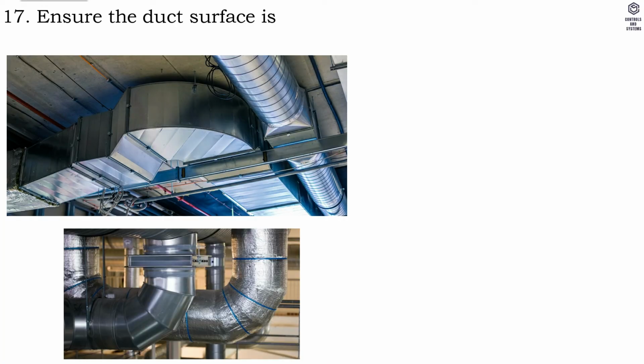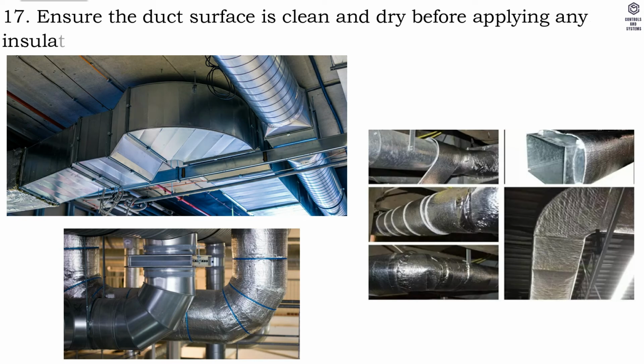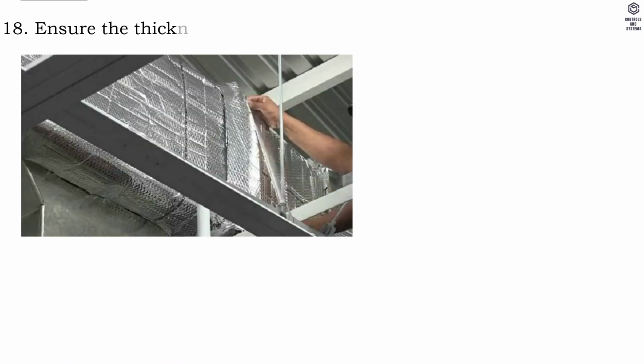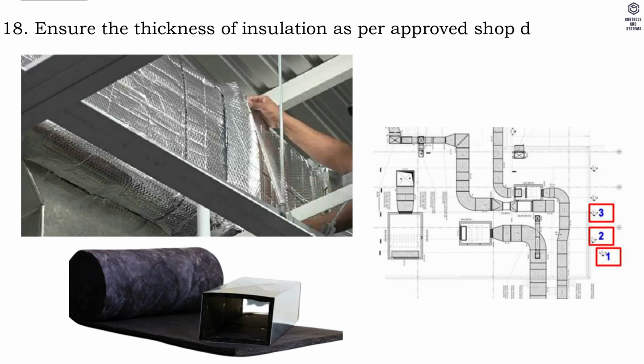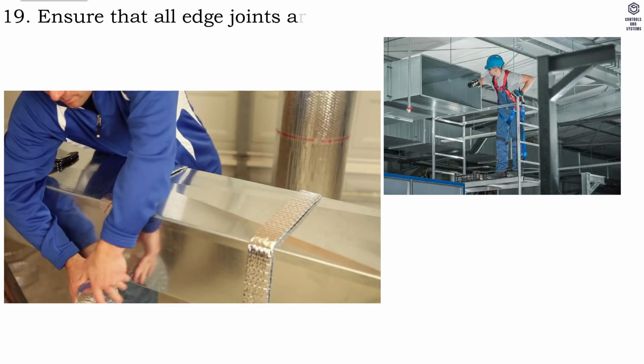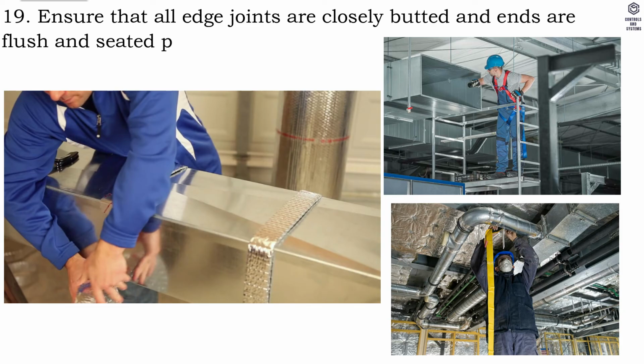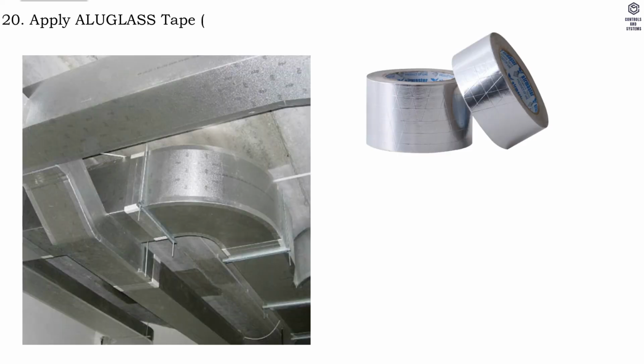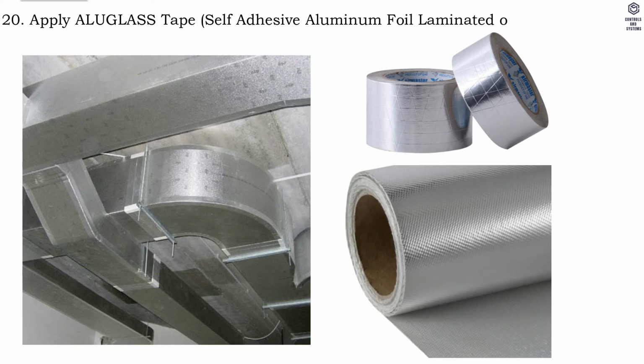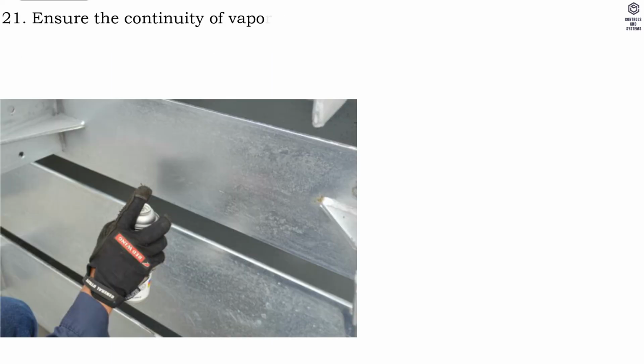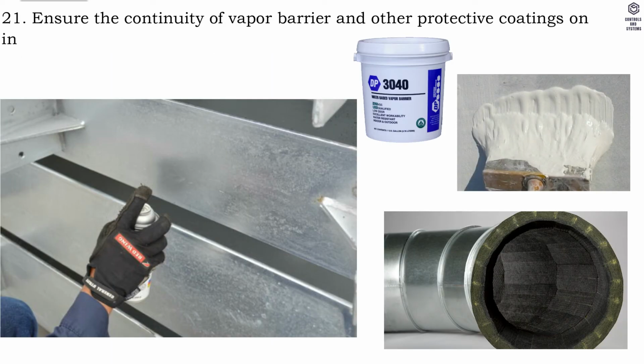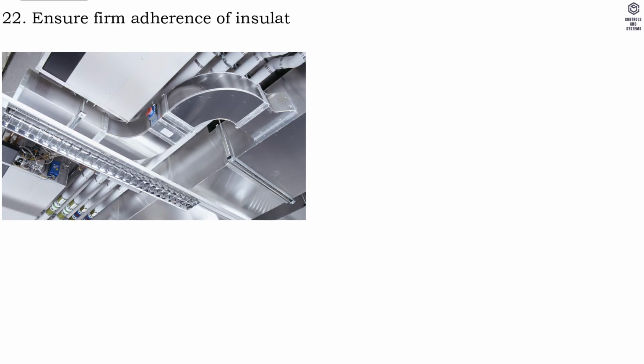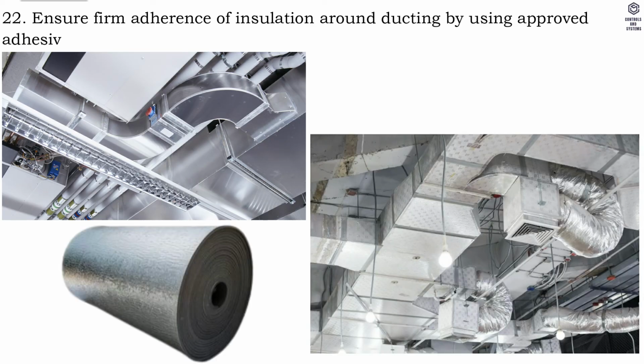17. Ensure the duct surface is clean and dry before applying any insulation material. 18. Ensure the thickness of insulation as per approved shop drawing. 19. Ensure that all edge joints are closely butted and ends are flush and seated properly. 20. Apply ALUGLASS Tape, self-adhesive aluminum foil laminated on glass fabric, at joints of insulation. 21. Ensure the continuity of vapor barrier and other protective coatings on insulation surface as well as at connections. 22. Ensure firm adherence of insulation around ducting by using approved adhesive between sheet metal and insulation material.